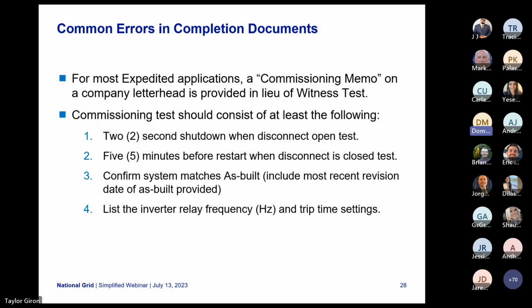Common errors now for the completion document package. For most or all expedited applications, that commissioning memo on a company letterhead will be provided in lieu of the witness test. That commissioning test should consist of the 2-second shutdown, 5-minute restart. You should confirm that the system matches the as-built and that the inverter relay frequency and trip settings are listed in the chart below. Next slide, please.